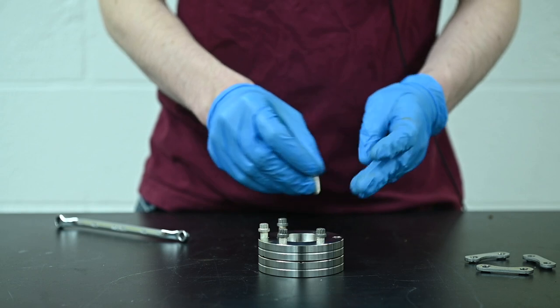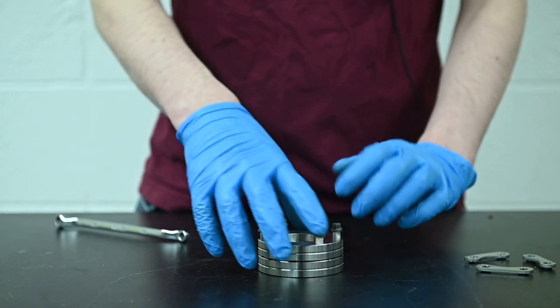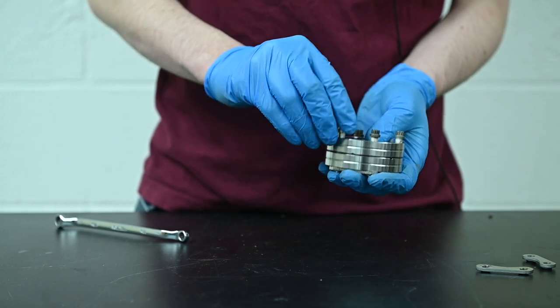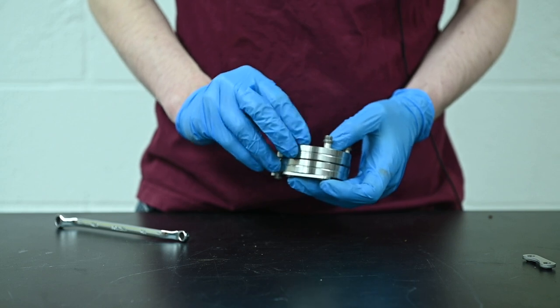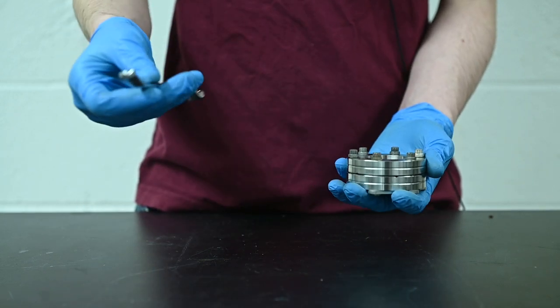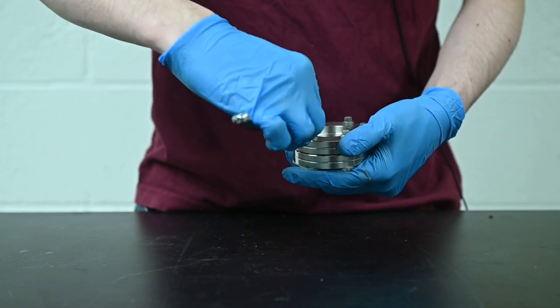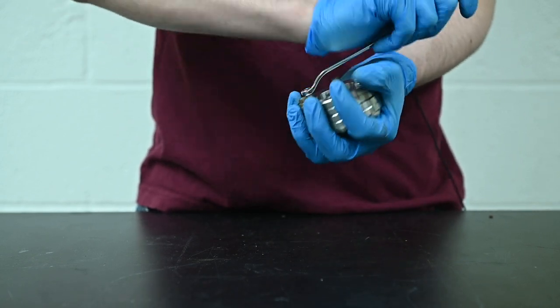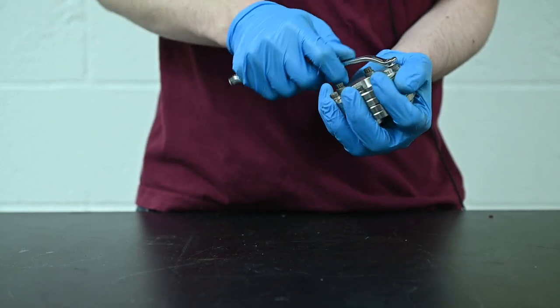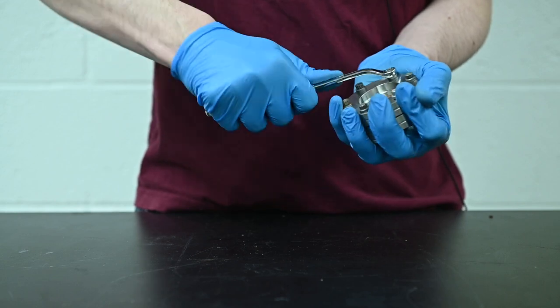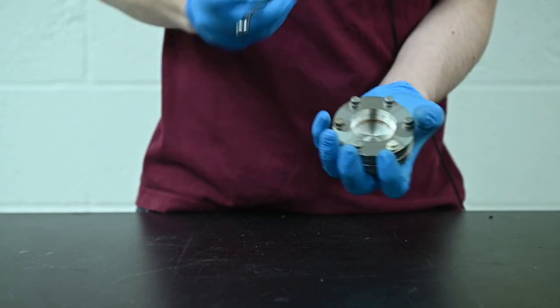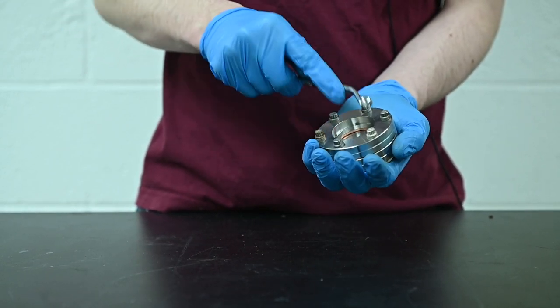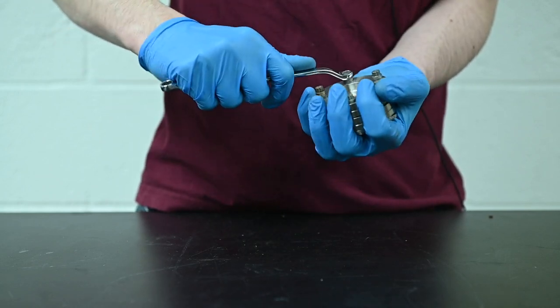Stainless bolts in stainless threaded holes will gall and seize, and you will not be able to achieve the required torque to crush the copper gasket. So we use silver-plated 12-point hardware. Additionally, we use nut plates on the backside so you don't need two wrenches to tighten. Tighten in a star pattern, going from one fastener to the opposite fastener all the way around the conflat flange, so that the gasket is evenly crushed.